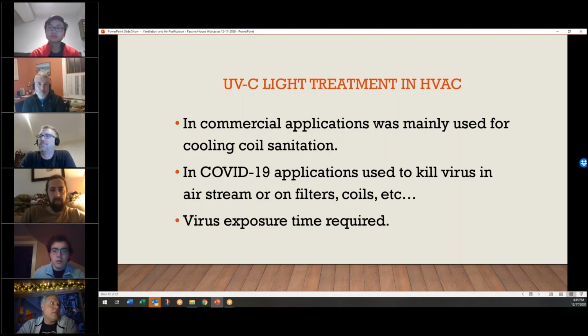So, we were doing one job in Boston where we had no return duct, and the units were those package units. There was no room to put a UVC light in, and we were actually considering putting them in the mech room, which was a return plenum. But then we were concerned with what's in this room that's going to be exposed to the light, and we'd have to have a door switch, because if somebody walks in, you want the UVC lights to go off. You don't want them to burn their eyes out because they're looking at UVC lights. So it's better applied inside a unit or in a duct where there's no chance of people staring at it and hurting themselves.